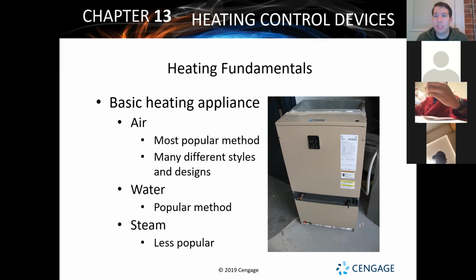Lastly is steam. Now, steam is not seen much in Virginia. You're going to see it if you go out to the mountains, or out in Farmville, over in Lynchburg, places like that, you're going to see steam boilers used pretty regularly. Steam boilers, if you've ever lived upstate in New York, Maine, Pennsylvania even, where it gets really cold, heavy winters, if you lived out in the Midwest area, you've probably dealt with a steam boiler in a house before. They've got massive cast iron radiators usually that take up a lot of space. They make a loud hammering pinging sound when they start up. It's a ping, bing, bing, bing, bing. It's really, really annoying. And that's typical for the steam systems.